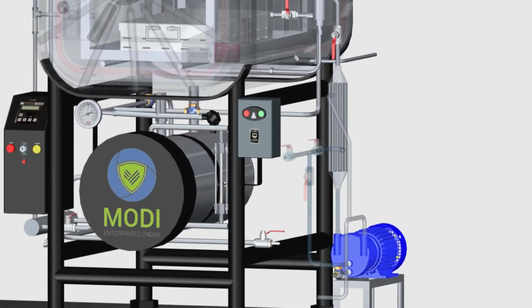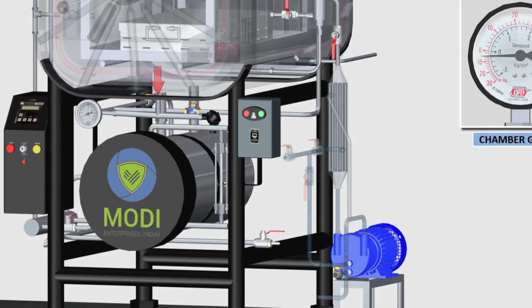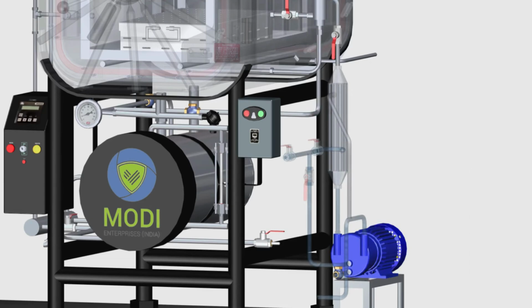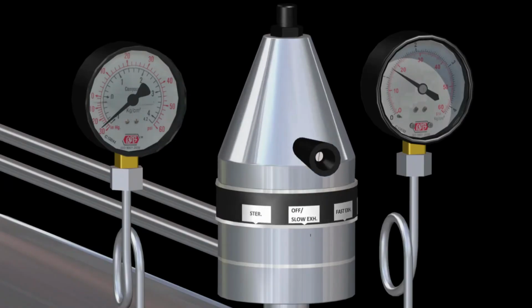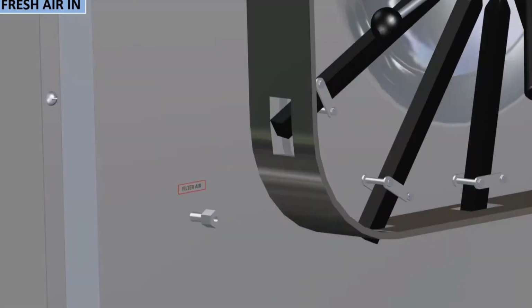Cycle validation. Indicators such as biological, chemical, or physical indicators are often used to ensure the sterilization parameters, time, temperature, pressure, have been met. Record keeping. Autoclaves usually generate printouts or digital records of the cycle, including temperature, pressure, and time data, which must be reviewed and archived for regulatory compliance.